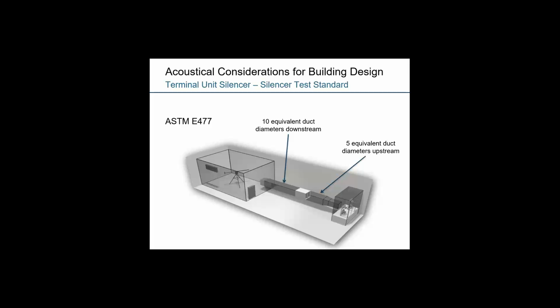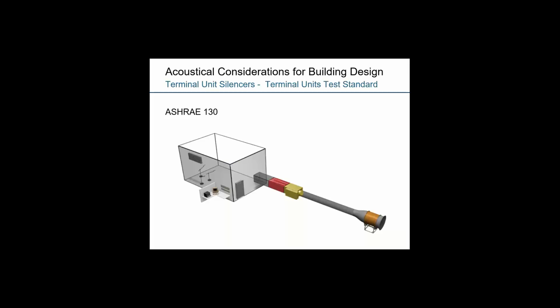When a silencer is close coupled with a terminal unit, the terminal inlet condition is now applied, and what you see in practical reality is that the damper positioning of the terminal and the close proximity can increase that discharge sound level. And because of that, this is where a quiet terminal unit with an appropriately selected and designed integral silencer really helps the situation. This device now is tested as an assembly to the appropriate ASHRAE 130 standard and can yield very low discharge sound levels, where it's now not two differing products tested to two differing standards. It's tested as a unique assembly to the appropriate standard, and it works very well for quiet air moving devices.